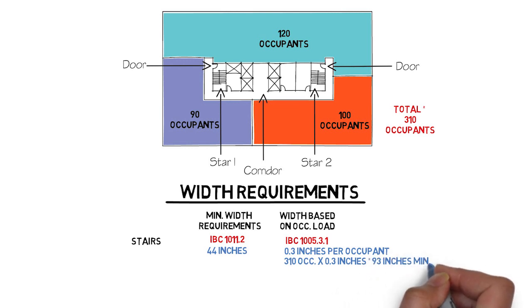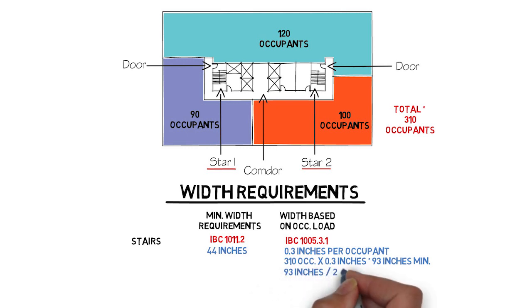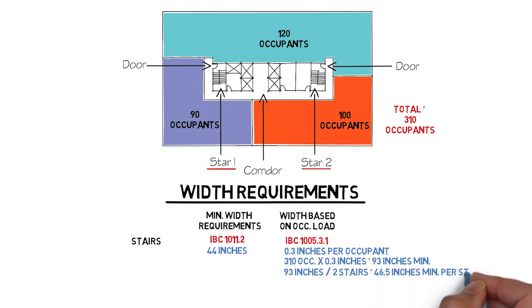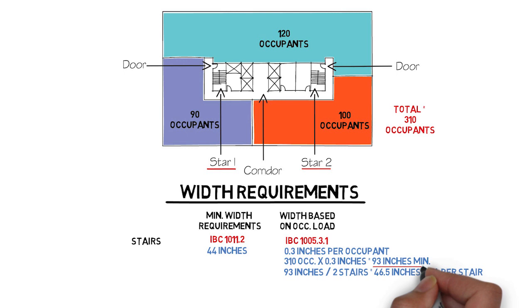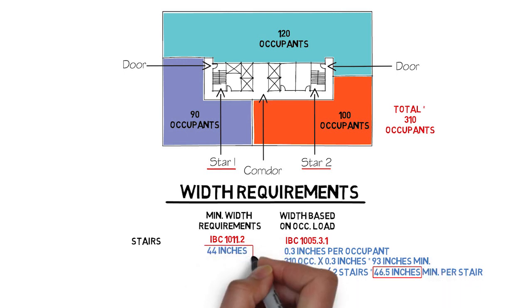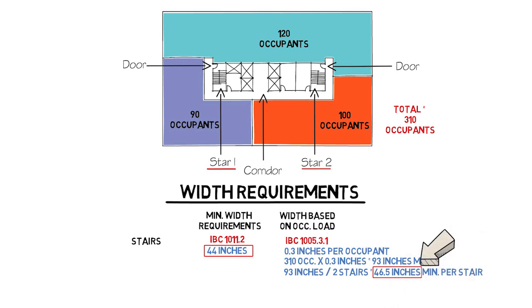In this example we have two stairs, which is normally the minimum number of stairs you need for a floor. Therefore, if we take the 93 inches and divide by two because there are two stairways, we are required for each stairway to be 46.5 inches wide minimum. It's important to note that these are minimums. 46.5 inches is greater than 44 inches, so our width based on occupancy is what we need to use since it is the most stringent requirement of the two. That is how wide our stairs have to be at minimum.